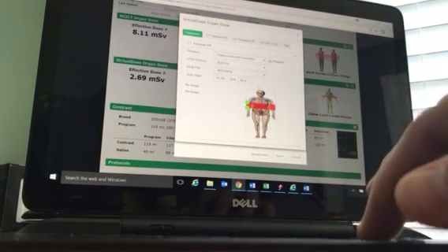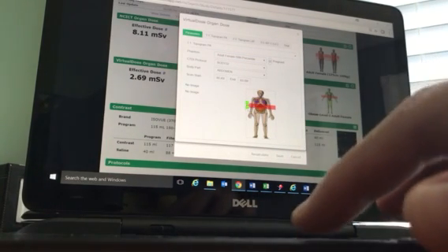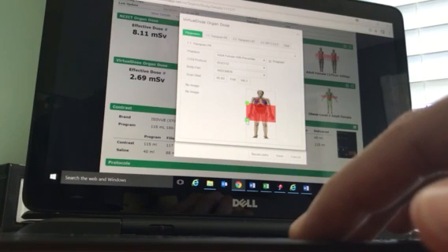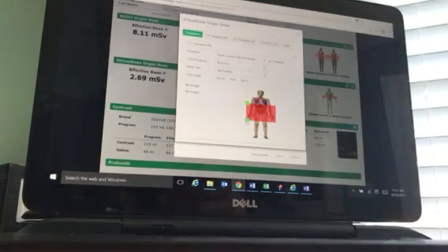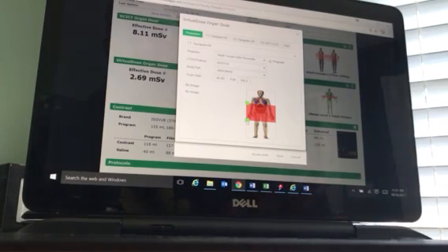The other thing that you can do is use this as a teaching tool. So you can scroll up and down to open the field of view and show the technologist the additional radiation that each organ may have received if the field of view was opened wider.